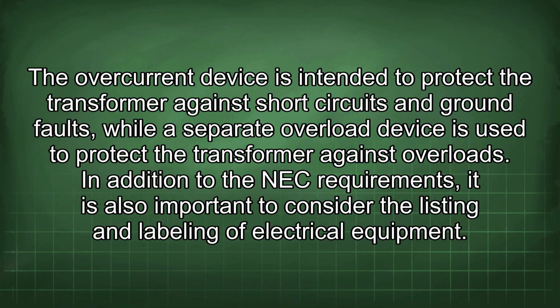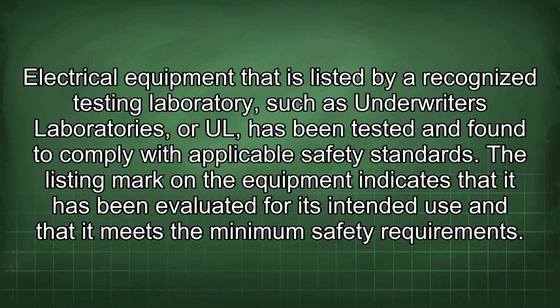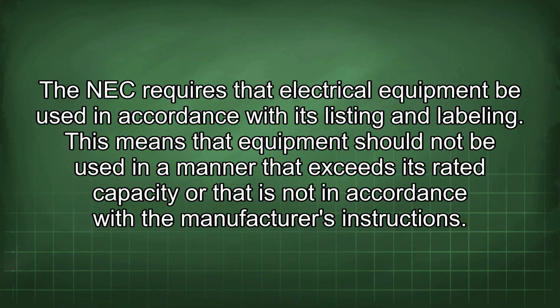In addition to the NEC requirements, it is also important to consider the listing and labeling of electrical equipment. Electrical equipment that is listed by a recognized testing laboratory, such as Underwriters Laboratories, or UL, has been tested and found to comply with applicable safety standards. The listing mark on the equipment indicates that it has been evaluated for its intended use and that it meets the minimum safety requirements. The NEC requires that electrical equipment be used in accordance with this listing and labeling. This means that equipment should not be used in a manner that exceeds its rated capacity or that is not in accordance with the manufacturer's instructions.